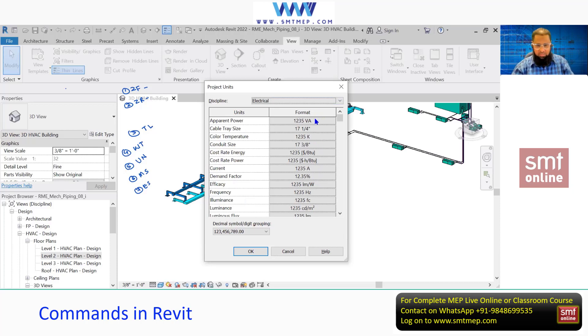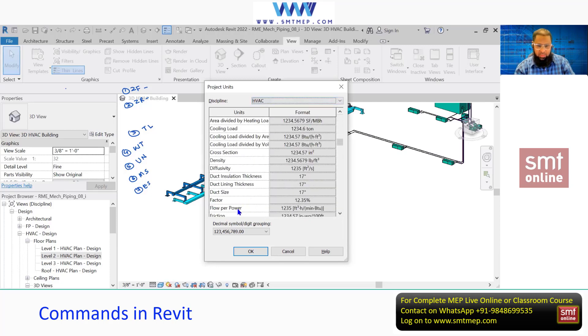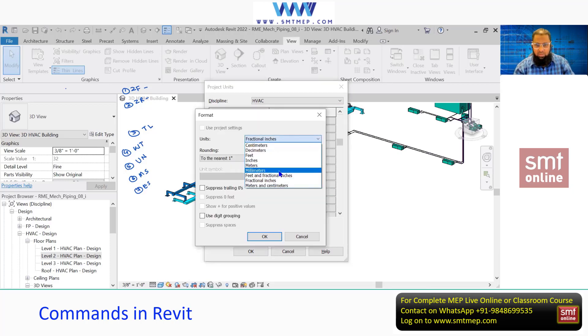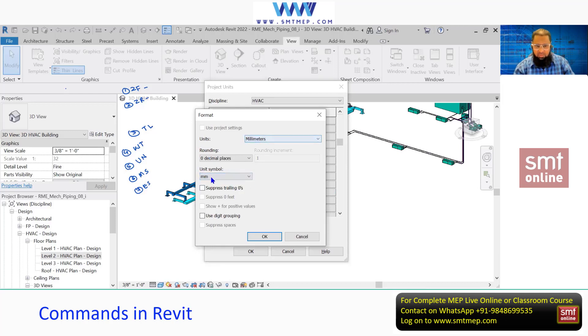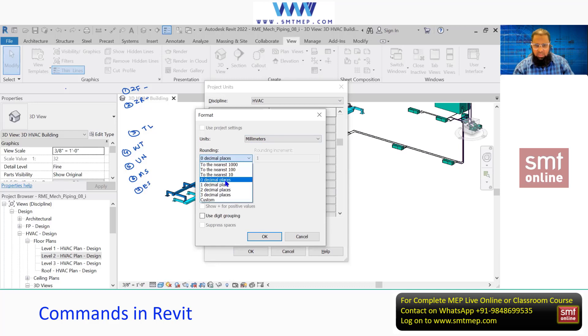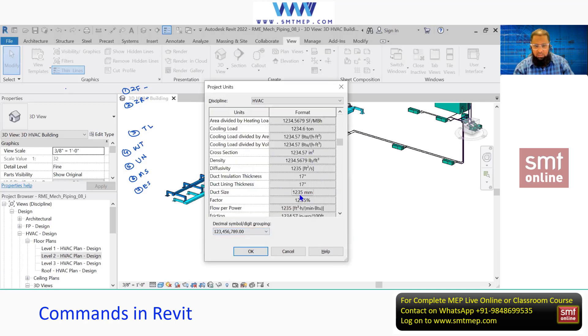In the English system, illuminance is in FC, not lux — lux is for metric. You can change units per requirement. For example, for duct size in the HVAC settings, by default it's in inches since this project uses an English template, but you can change it to millimeters. Select millimeters and set decimal precision to zero — so duct sizes like 500mm x 300mm will display correctly. After changing this, all available sizes with tags will automatically update.